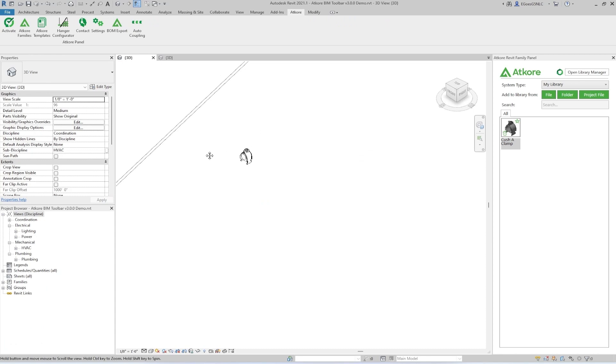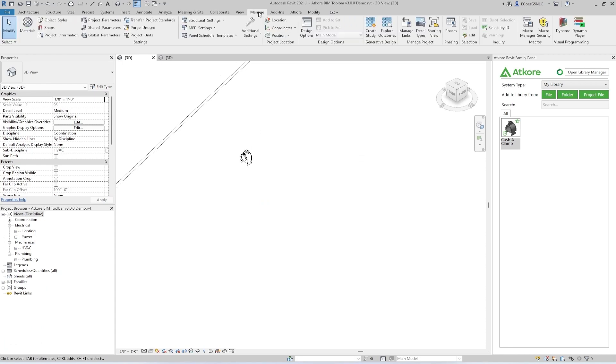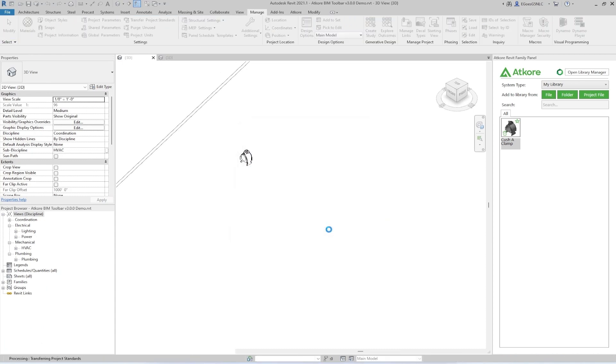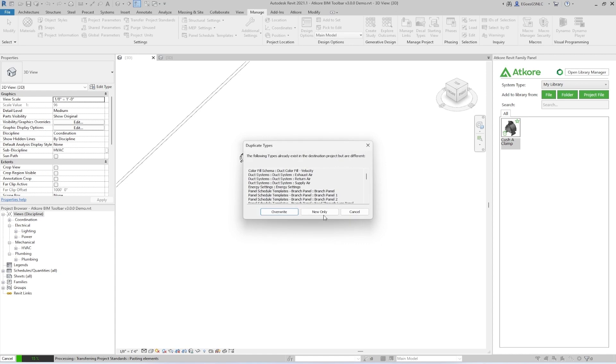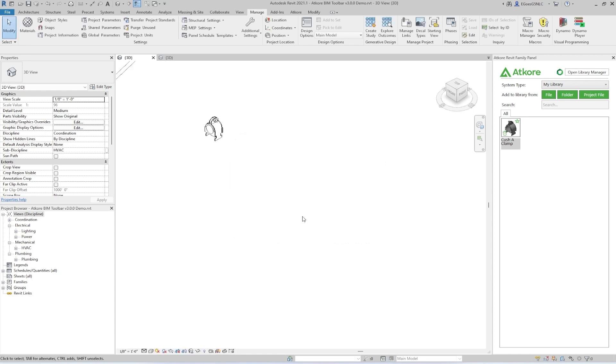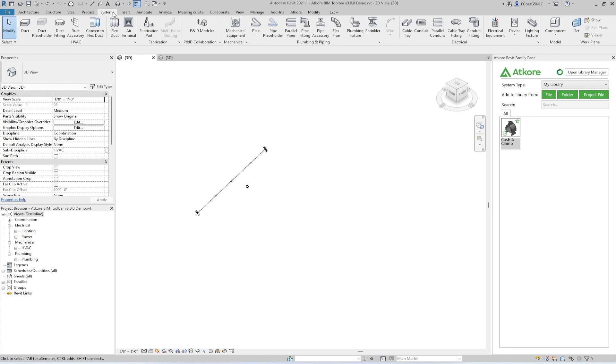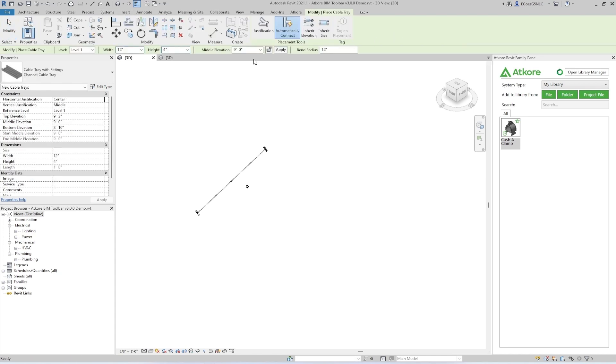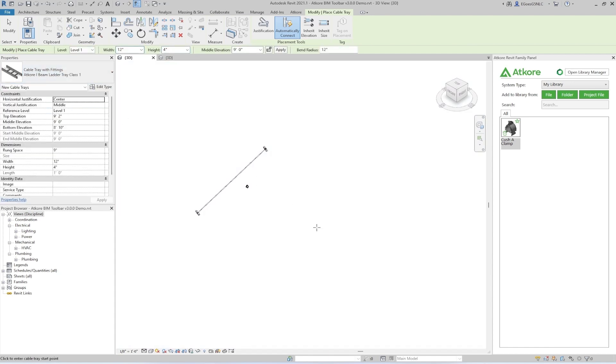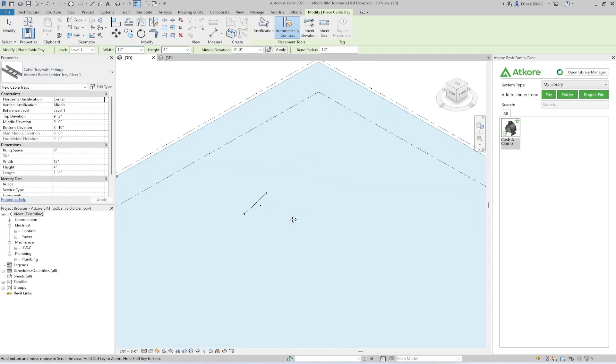These templates can then be transferred into your project to make drawing with Atkore product as easy as drawing with the default Revit system families. To do this, go to the Manage tab, hit Transfer Project Standards, and then transfer the correct template into your project. After it is transferred in, you're going to go to the Systems tab, and then select the system that you would like to lay out. Once there, make sure you select the Atkore product from the dropdown. Now you can draw like normal.